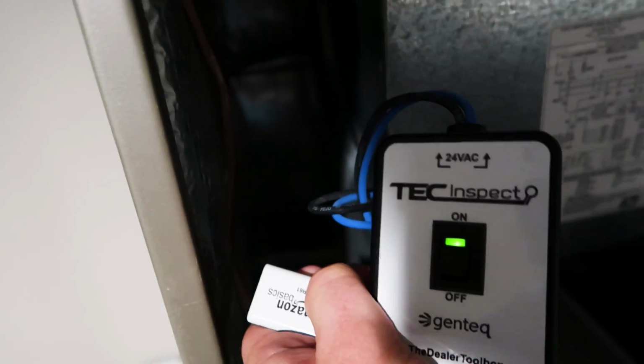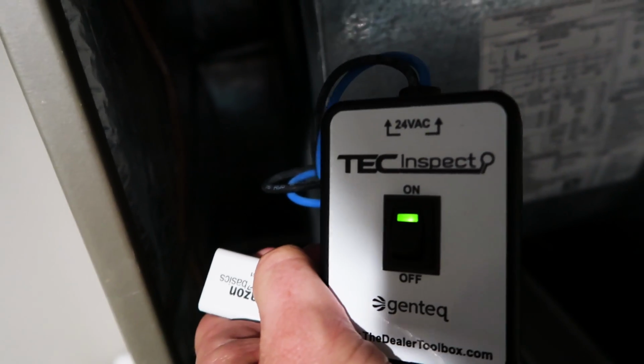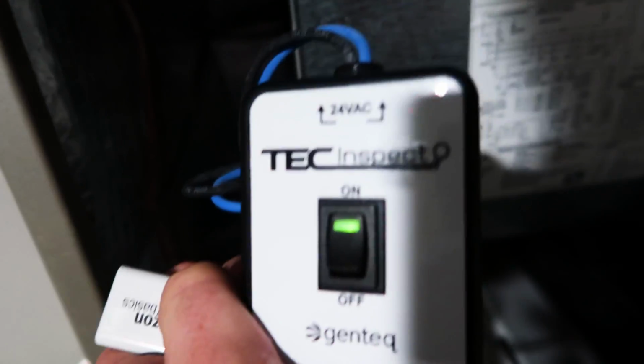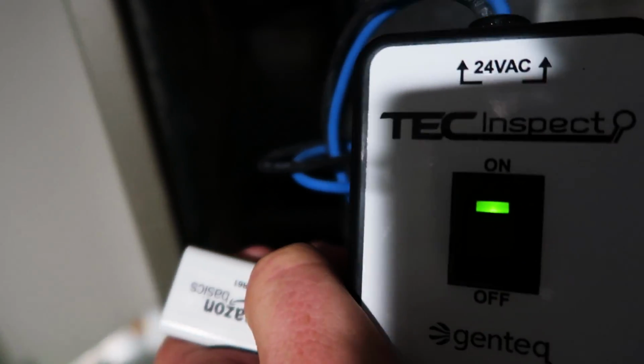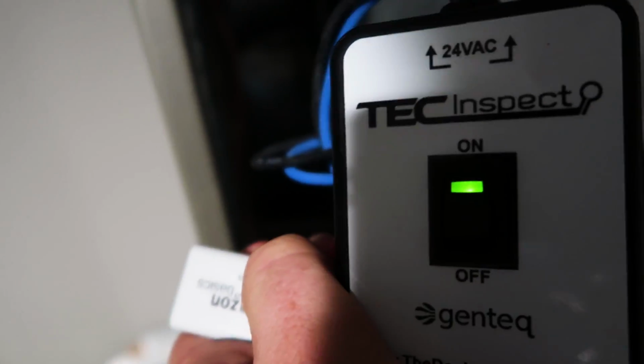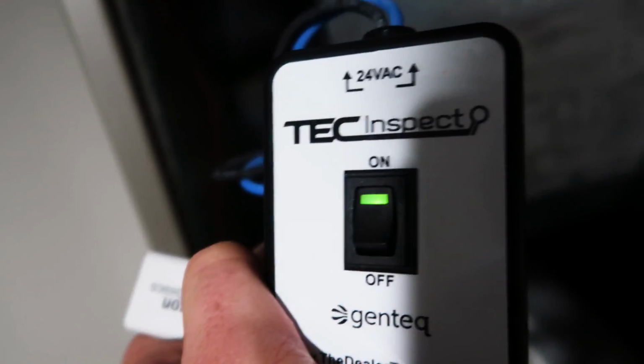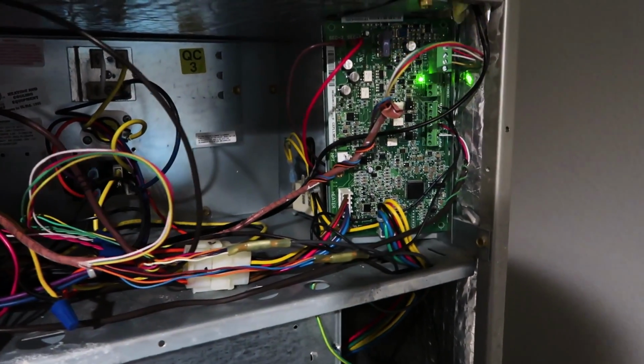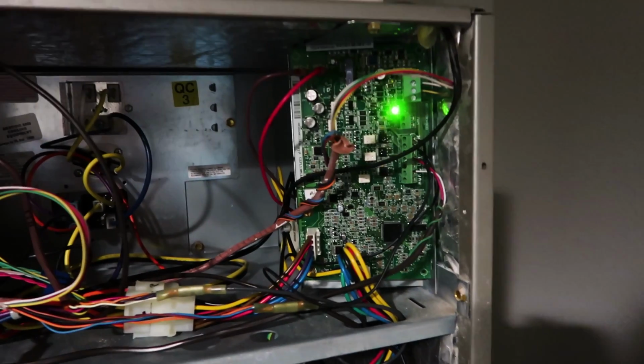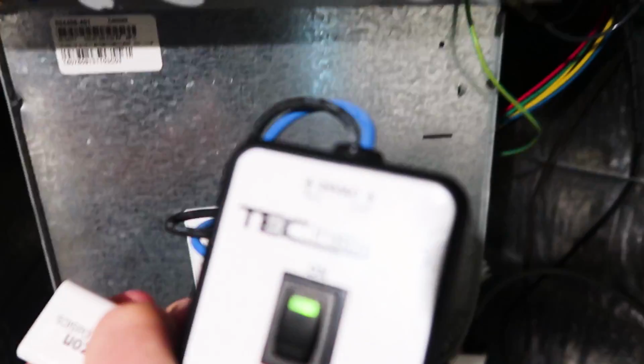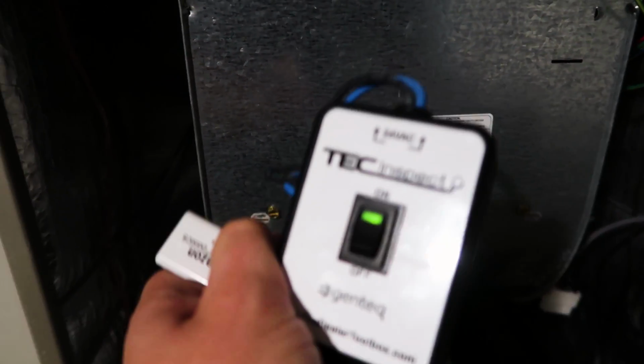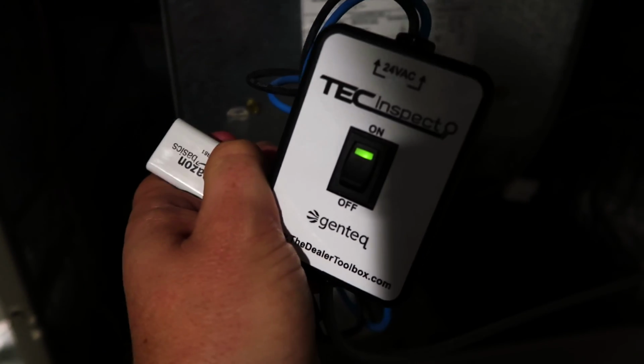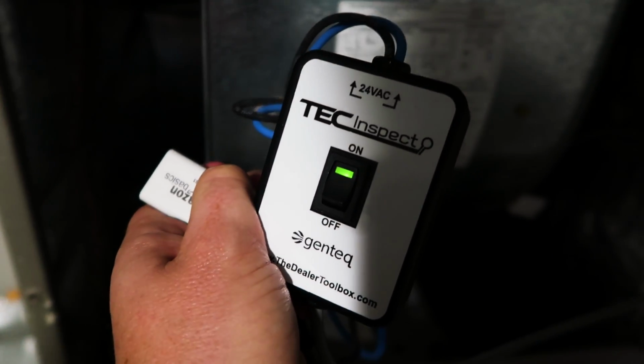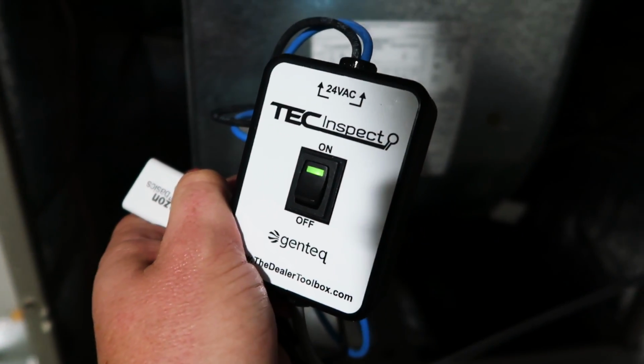Again, of course they are because I just replaced them, but that's a good diagnostic test to prove that you don't have a problem with the motor and module. So if it wasn't working, then you did this and it did work, that tells you it's either in the harness or the control board feeding it. If it wasn't running, you connect this, flip it on, and then it does run. This just basically proves that the motor and module are both working. And they are, because I just replaced them.